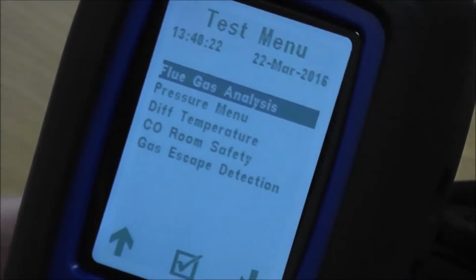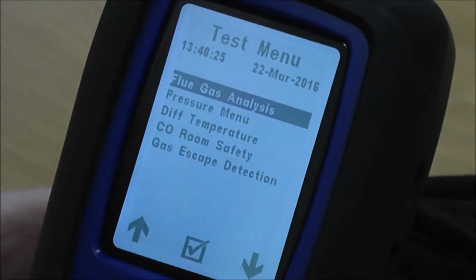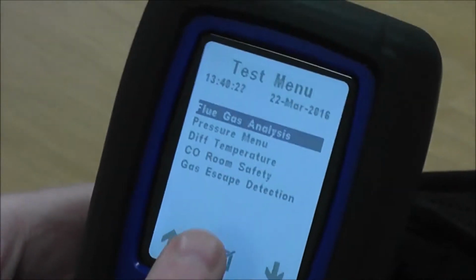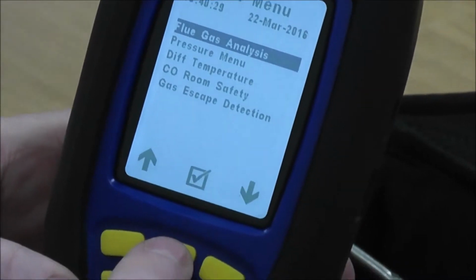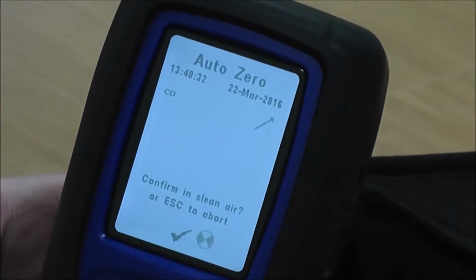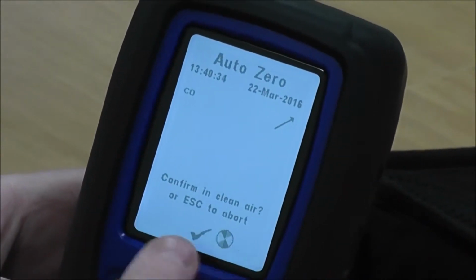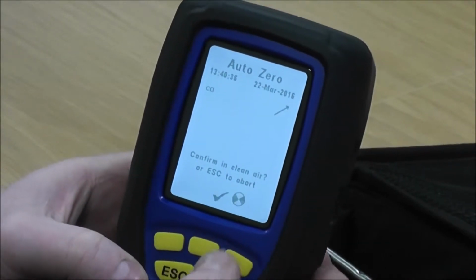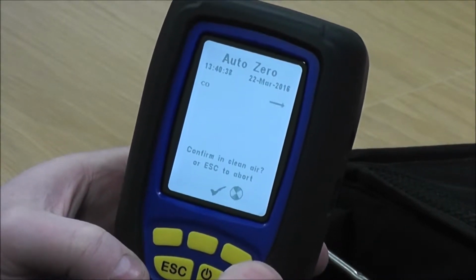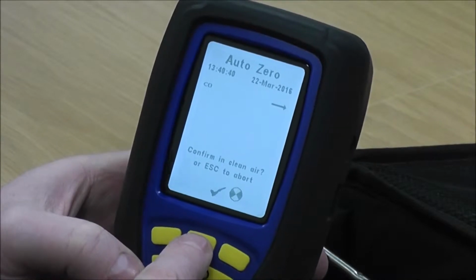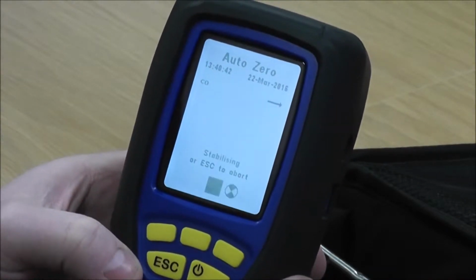And then that gets us through to the test menu. Now, if I pick flue gas analysis, and I'll press the top middle button to go into that, it's saying auto 0. So now it's asking me to confirm I'm in clean air. As I said, that would normally be outside, or you'd be hanging the flue probe outside a window. So I'm going to press to confirm that I'm in clean air.